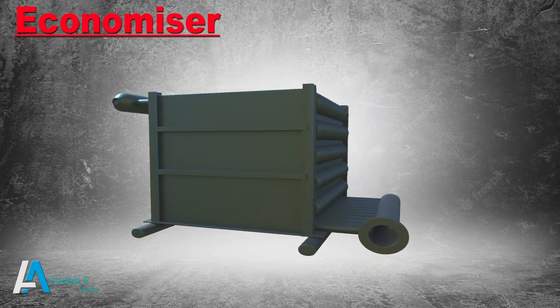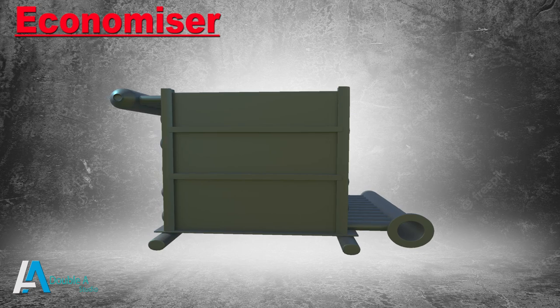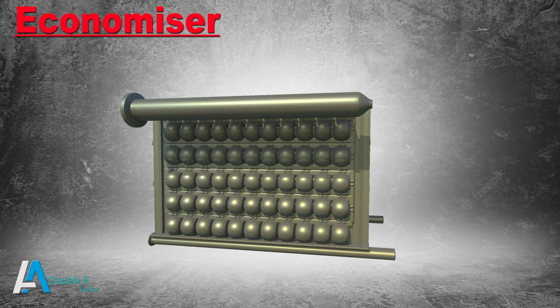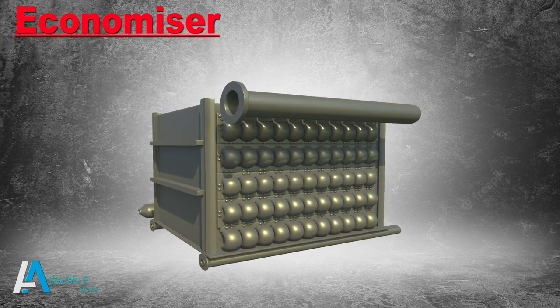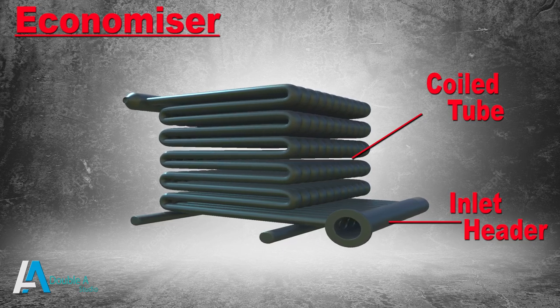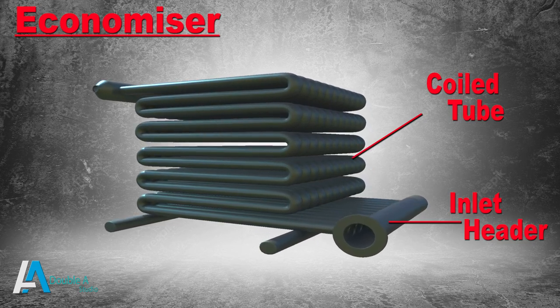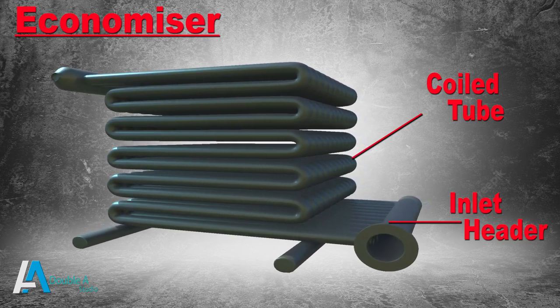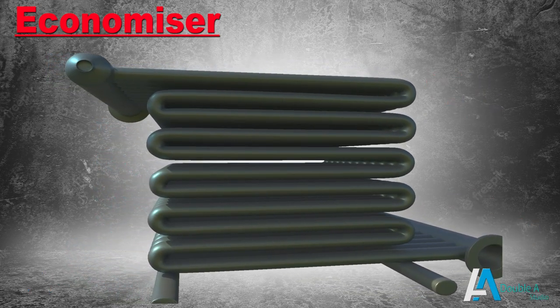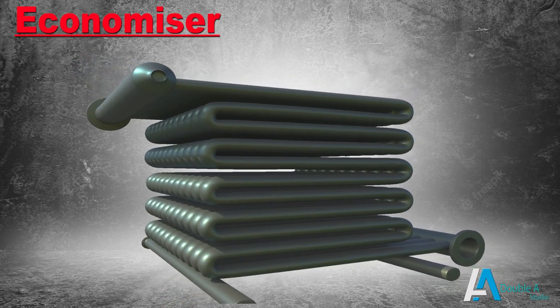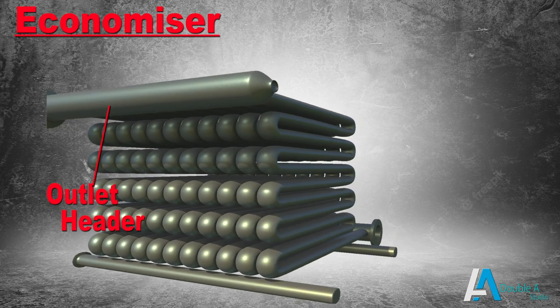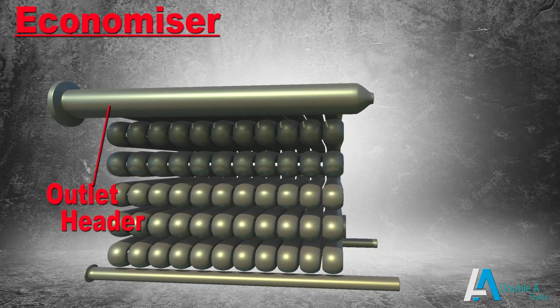The flue gases coming out of the boiler contain a large amount of heat. To recover this heat, the economizer gets installed in the flue gas path before the exit of the boiler. It saves energy by recovering heat from hot flue gases and utilizing it to preheat feed water.